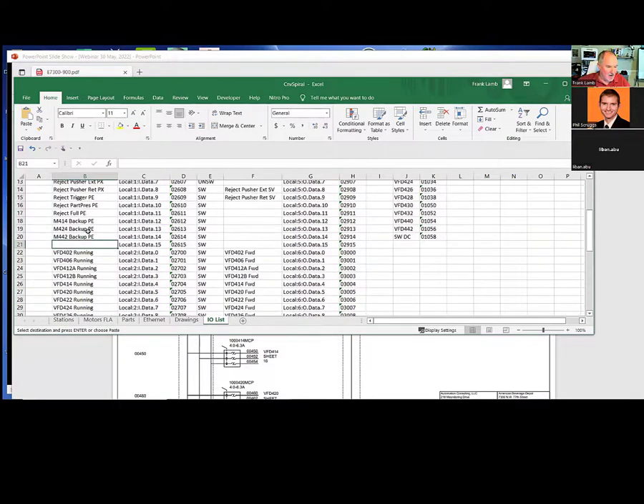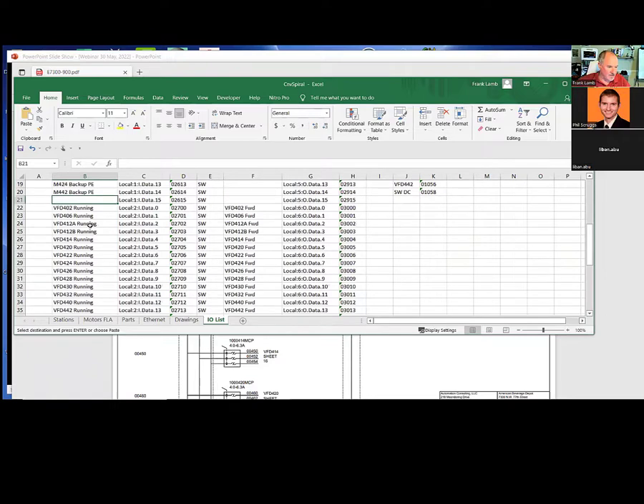A lot of the IO here has to do with simply monitoring the drives—is the drive running? I've got a running input for every single drive. Now you might ask why I didn't use Ethernet IP to connect to the drive like I'm going to do with the cameras. The answer is we're having a global supply chain shortage, and right now anybody is having a hard time getting drives.